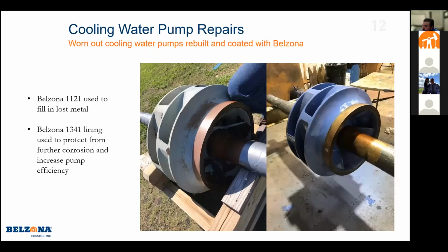Same scenario, you see some coating failure causing a little bit of corrosion and pitting. We used the same paste grade to fill in lost metal, and then our hydrophobic lining that increased pump efficiency and decreased amp draw.